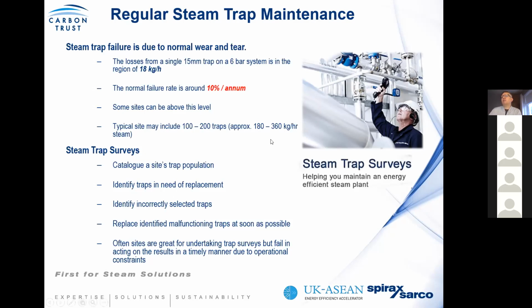So what that means is that this is where you should be. Reality, best in class is 5%. From our experience, we're seeing failure rates as high as 30% for some industries. So you can see that your leakage rate can be quite significant. So what you should be doing is cataloging your trap population and identifying the traps in your system. Also, there's no one best fit trap.